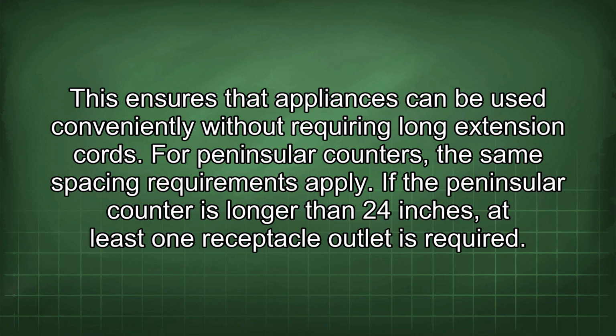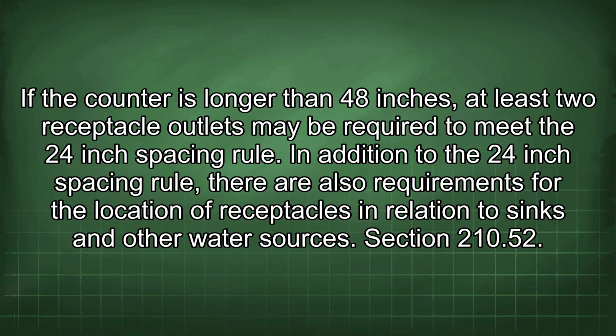For Peninsular counters, the same spacing requirements apply. If the Peninsular counter is longer than 24 inches, at least one receptacle outlet is required. If the counter is longer than 48 inches, at least two receptacle outlets may be required to meet the 24-inch spacing rule. In addition to the 24-inch spacing rule, there are also requirements for the location of receptacles in relation to sinks and other water sources.